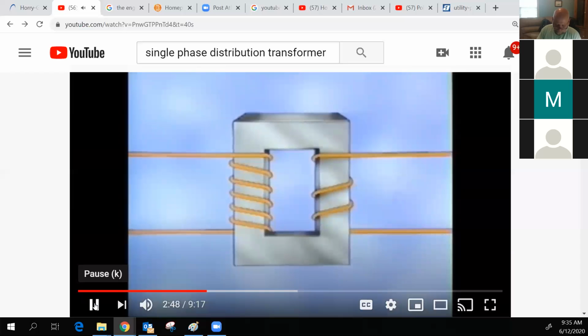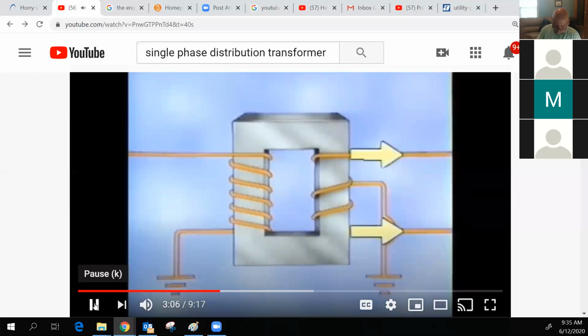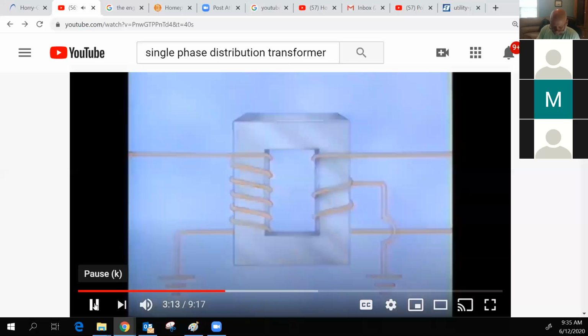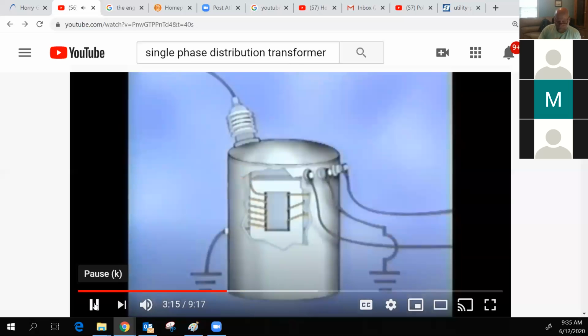In this example of a step-down transformer, one end of the primary winding is grounded. A tap coming off the center of the secondary winding is also grounded. This results in one primary lead coming into the transformer and two secondary leads, plus a ground coming out of the transformer. We'll use this simplified illustration to show you how the basic elements are arranged in a typical pole-top transformer.